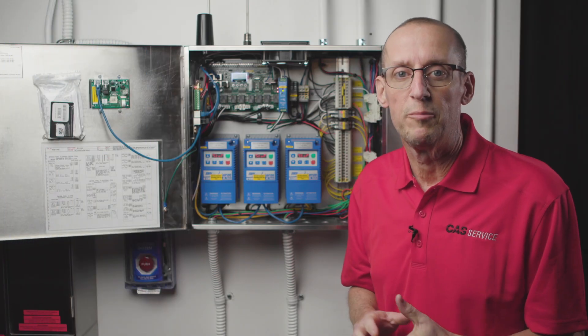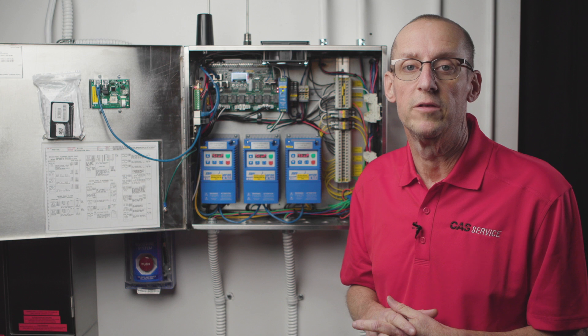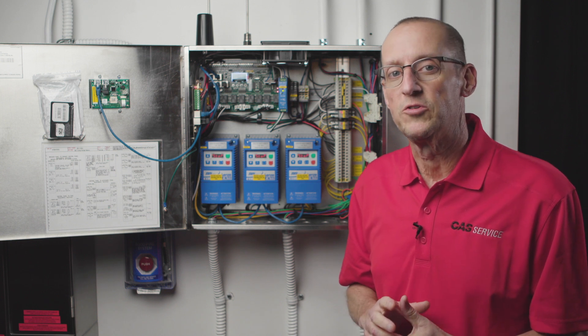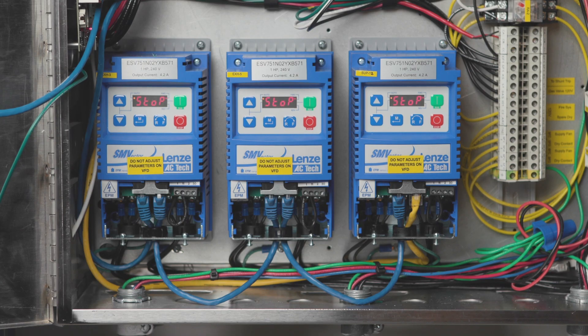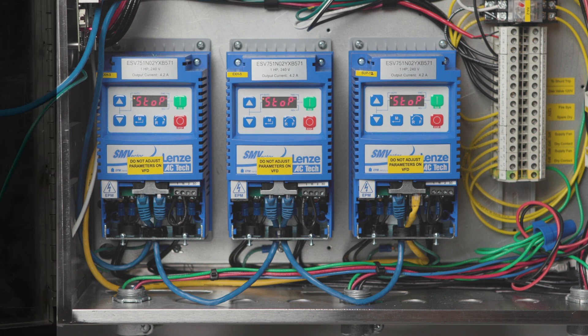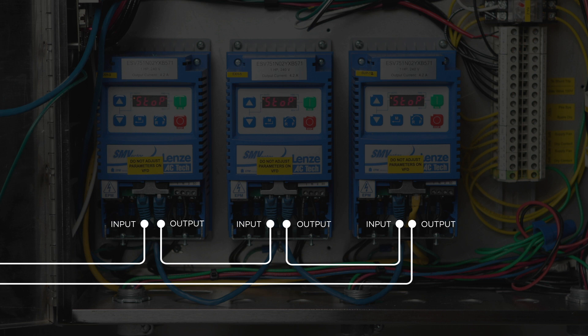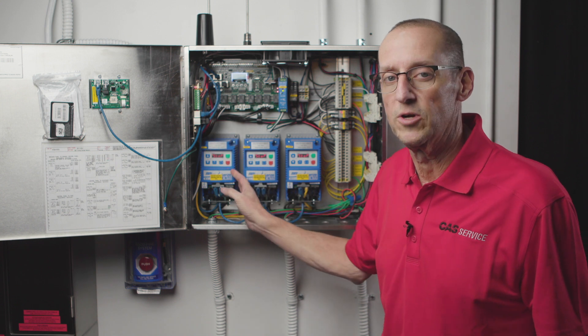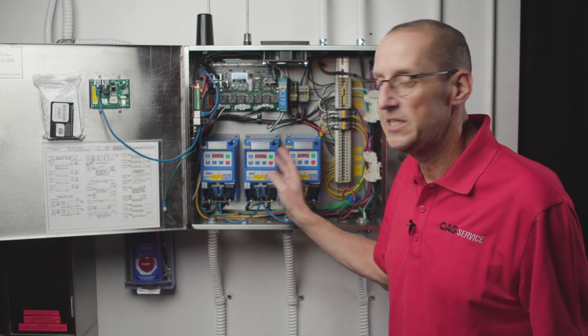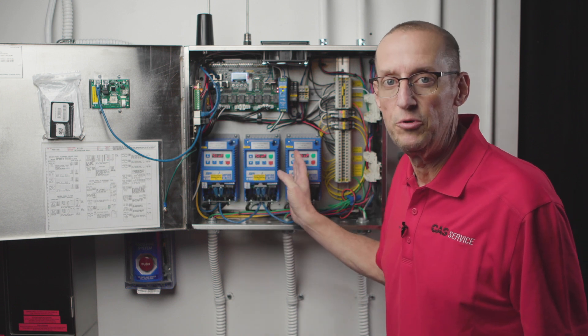First let me explain what a Modbus network is. A Modbus network is an internal device network where you have several devices all connected together, daisy-chained together with CAT5 cable — all this blue cable here. So for example, we have three VFDs, and because they're all daisy-chained together on one network with one single cable, each device has to have its own unique address.